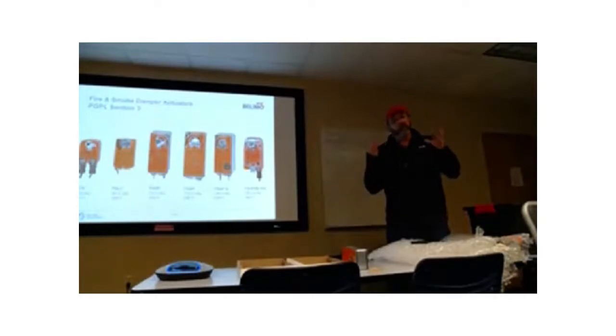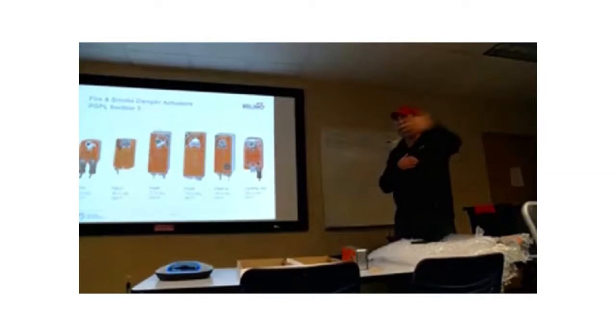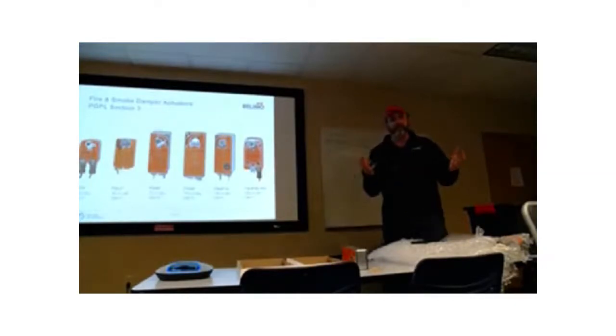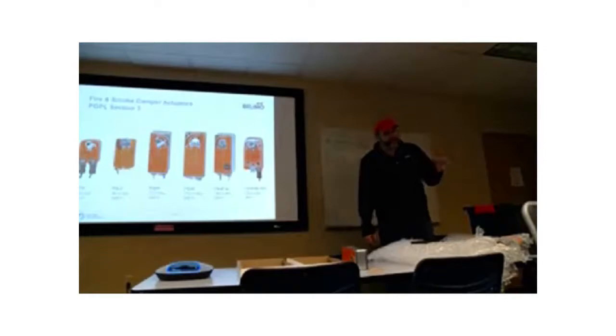The UL does not address maintenance, right? So what happens if something there fails? What do you do? The UL does not address maintenance, they just say it needs to be operable. So technically, if you replace the fire smoke damper actuator on an assembly, you have technically violated the UL listing.